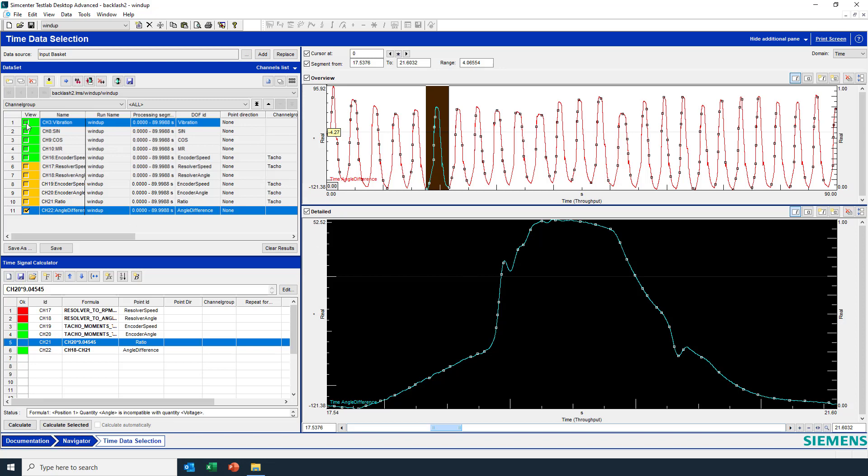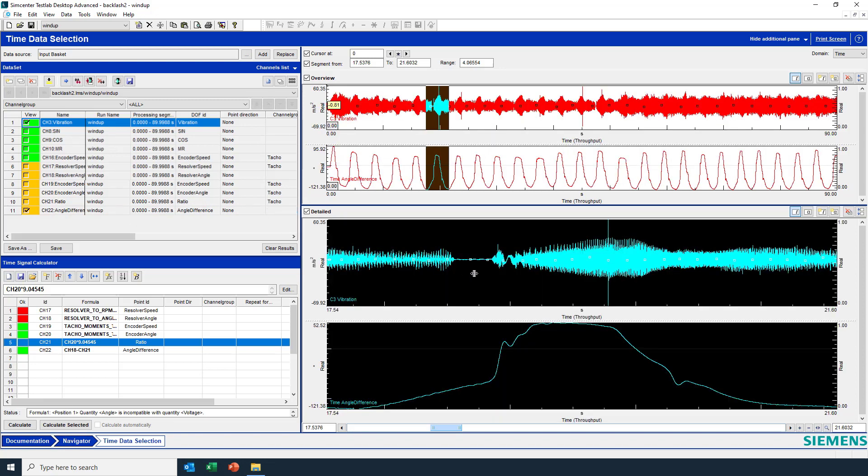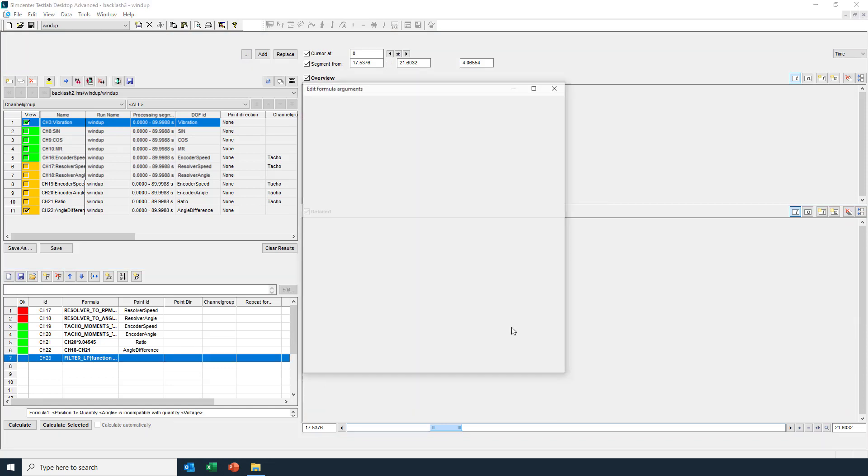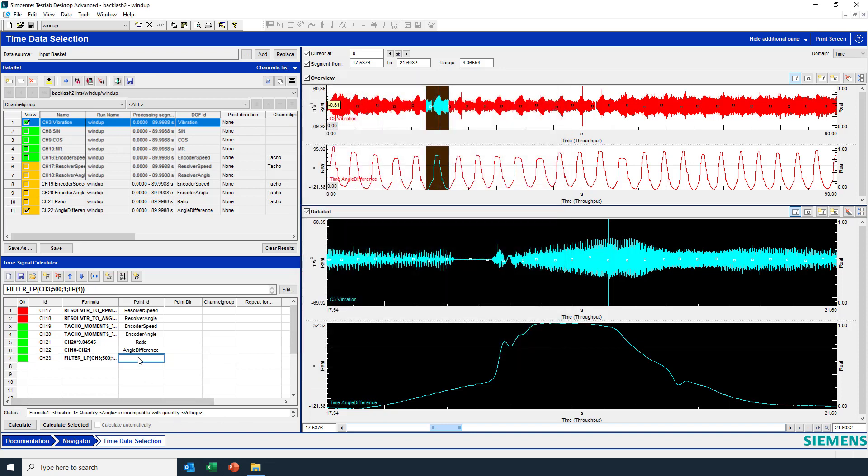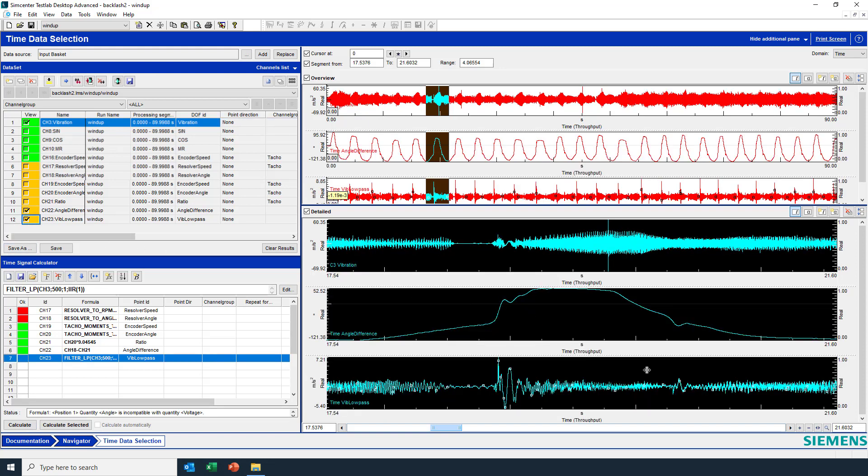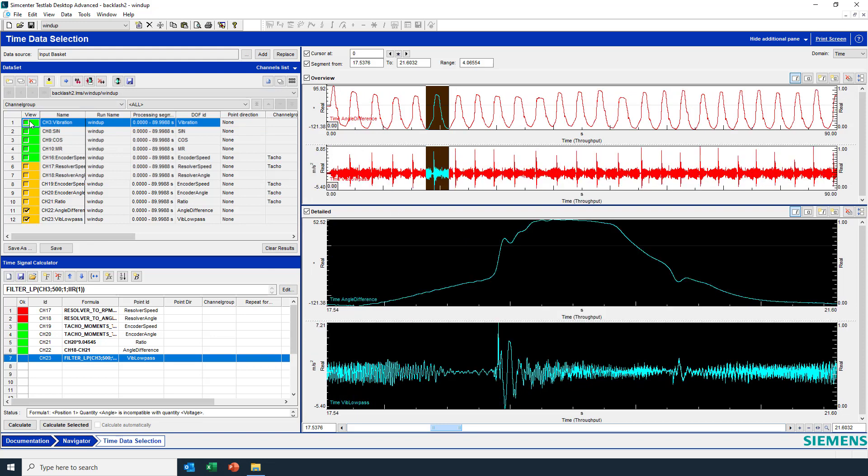If I look at the vibration at the same time, maybe there's something going on here. Now the vibration it's not totally clear, but maybe if I do a filtering. Channel three. I'll do a low pass filter. Looks pretty sharp here. So vibe low pass. Calculate again. Let's look at that low pass vibration. And yeah, I can see that there's a disturbance in the vibration that definitely corresponds to the glitch in the angular difference between the final drive and the electric motor. Thanks, and I hope that was helpful.